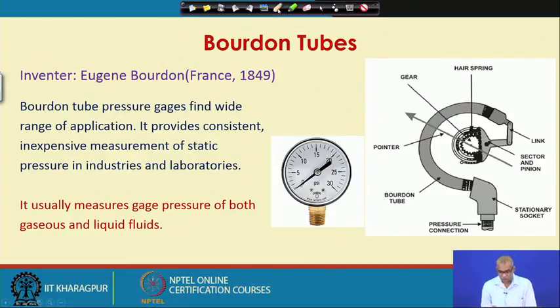So, a Bourdon tube pressure gauge will look like this. You perhaps have seen this in laboratories. What you see is a pointer and the scale. The scale is in PSI, the unit of pressure, pounds per square inch. Now, as we apply pressure inside this, this is the connection available for application of pressure. This is connected to a pipeline through which a fluid is moving and you want to measure the pressure of the fluid. As you apply pressure inside, there will be movement of this pointer, and from the position of the pointer against the scale, you can read the measurement of the pressure.